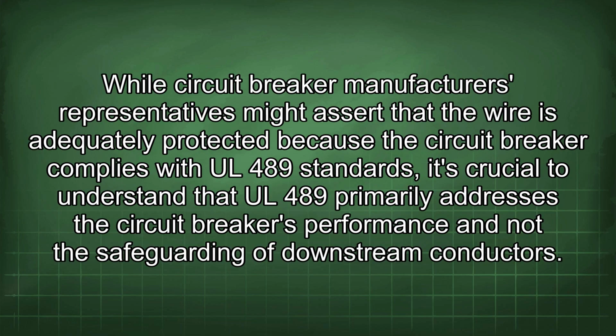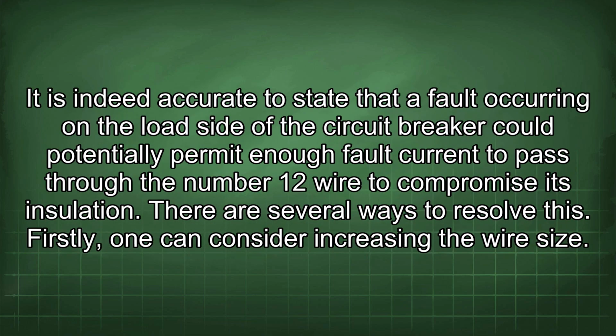While circuit breaker manufacturers' representatives might assert that the wire is adequately protected because the circuit breaker complies with UL 489 standards, it's crucial to understand that UL 489 primarily addresses the circuit breaker's performance and not the safeguarding of downstream conductors. It is indeed accurate to state that a fault occurring on the load side of the circuit breaker could potentially permit enough fault current to pass through the number 12 wire to compromise its insulation.